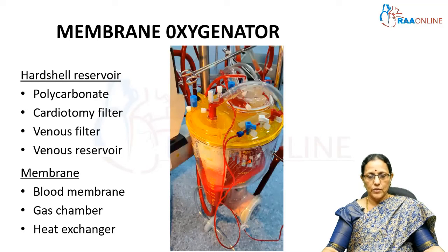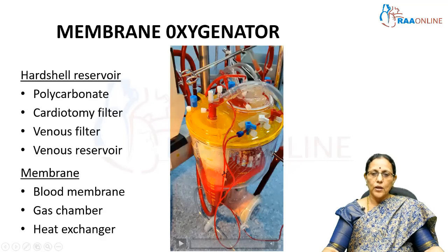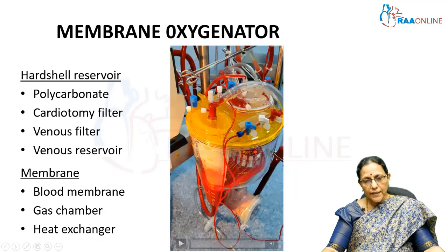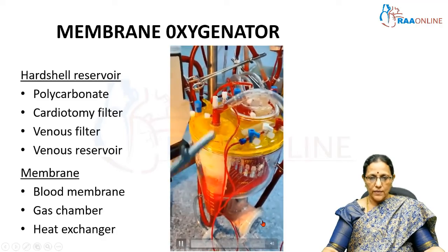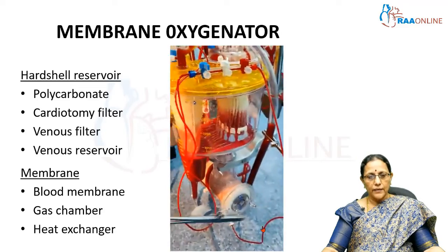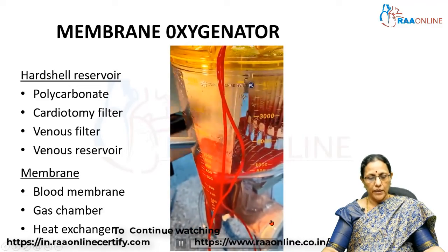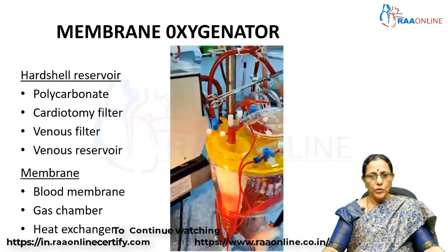The current membrane oxygenator has a hard shell reservoir and a membrane portion. The venous reservoir is made up of hard shell polycarbonate material, making it easily visible and sturdy. Inside the venous reservoir there are two types of filters — the venous filter and the cardiotomy filter. It is into the cardiotomy filter that the cardiotomy and venous suction drain. The membrane itself has three portions: the blood column, the gas column, and an integral heat exchanger. Gas enters and oxygenates the blood, and the heat exchanger inside the membrane either cools or warms the patient during cardiac surgery.